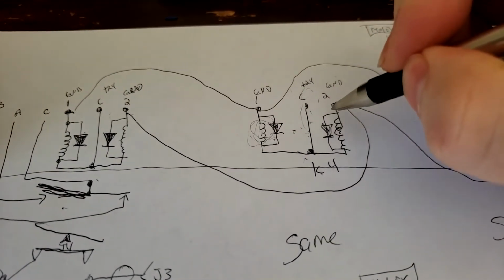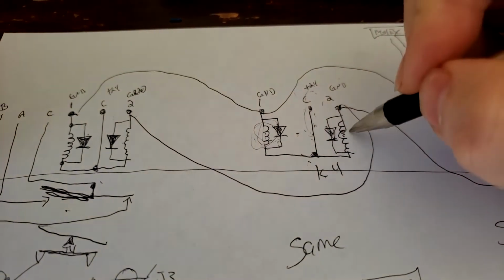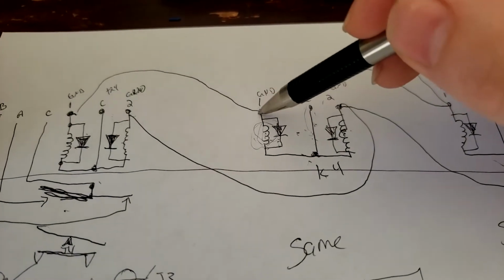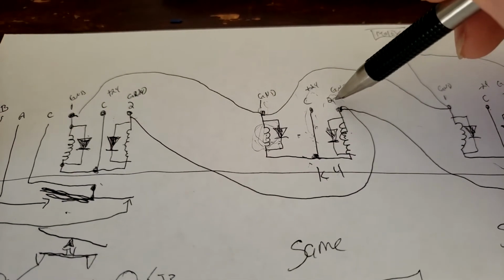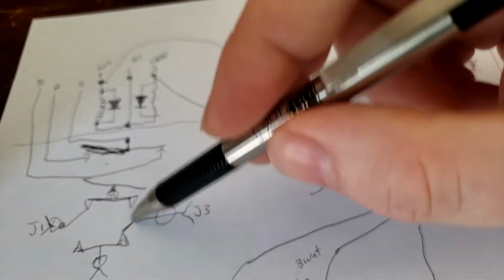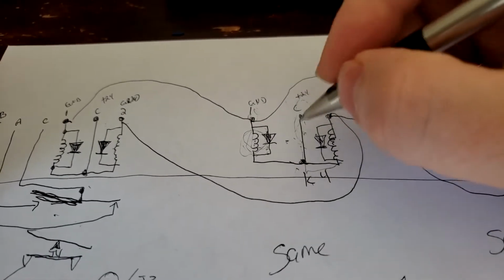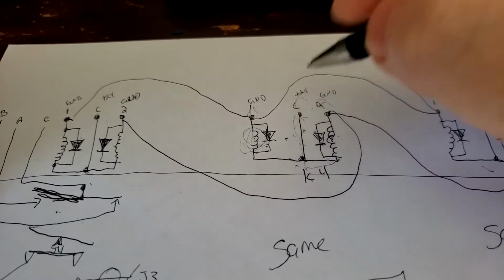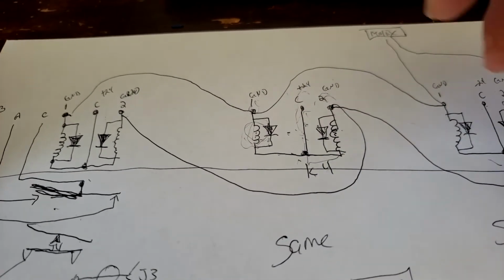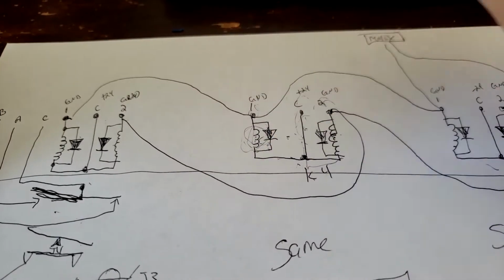Since this is a latching relay, we know that in order to induce a separate state, a change, when we remove the ground from here and put it onto terminal two, that's the only way to make the change with your contacts here for the output. Otherwise, it remains the same.